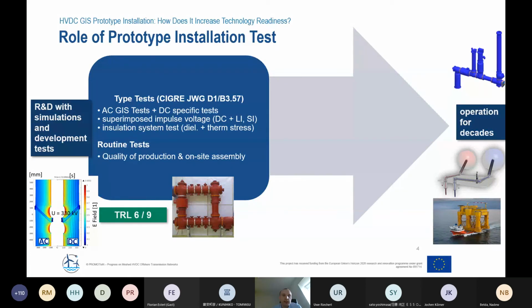However, for a new technology like HVDC GIS, the technology readiness level would be evaluated a bit lower than for an established technology. So out of the 9 technology readiness levels, at the start of the PROMOTION project, we would have evaluated HVDC GIS at level 6 out of 9. So there are some type tests, or at least recommendations for type tests, for example from the CIGRE pre-standardization work, where we have DC-specific type tests added, like superimposed voltage testing or the insulation system test that combines dielectric and thermal stresses.